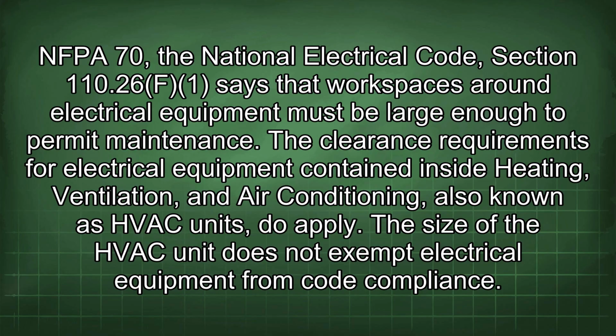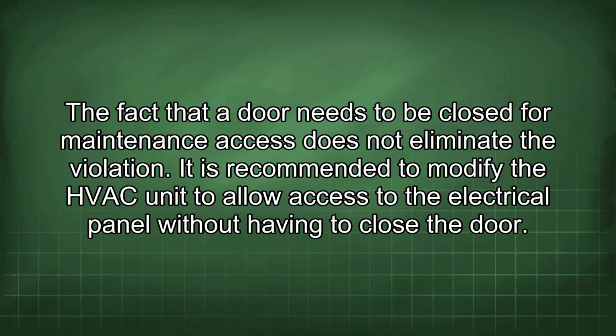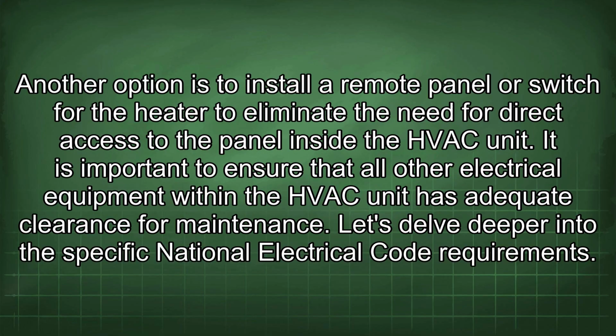NFPA 70, the National Electrical Code, Section 110.26 says that workspaces around electrical equipment must be large enough to permit maintenance. The clearance requirements for electrical equipment contained inside heating, ventilation, and air conditioning, also known as HVAC units, still apply. The size of the HVAC unit does not exempt electrical equipment from code compliance. The fact that a door needs to be closed for maintenance access does not eliminate the violation. It is recommended to modify the HVAC unit to allow access to the electrical panel without having to close the door. Another option is to install a remote panel or switch for the heater to eliminate the need for direct access to the panel inside the HVAC unit. It is important to ensure that all other electrical equipment within the HVAC unit has adequate clearance for maintenance.